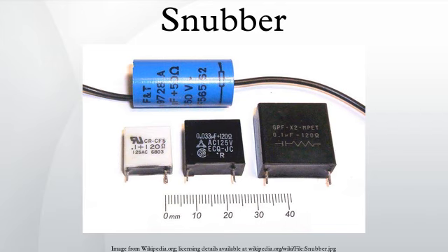Mechanical systems. Controlling pipe movement with mechanical snubbers. Snubbers for pipe and equipment are used to control movement during abnormal conditions such as earthquakes, turbine trips, and safety relief valve closure. Snubbers allow for free thermal movement of a component during regular conditions, but restrain the component in irregular conditions. A hydraulic snubber allows for pipe deflection under normal operating conditions. When subjected to an impulse load, the snubber becomes activated and acts as a restraint in order to restrict pipe movement. A mechanical snubber uses mechanical means to provide the restraint force.